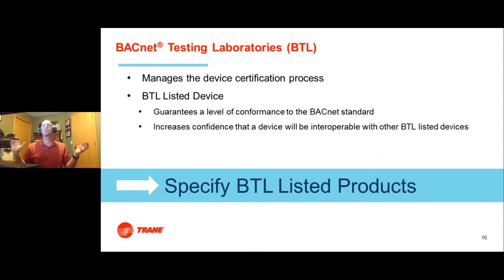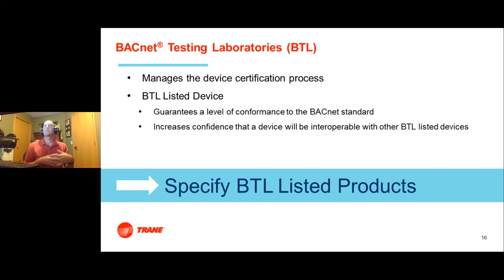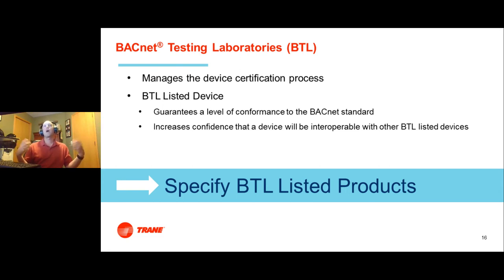As we talked about open standards, there's a testing arm for BACnet called BACnet Testing Laboratories, or BTL. You submit a product, it goes through standardized testing, and if it passes it becomes a BTL-listed device. This really helps increase our confidence that we'll have good interoperability between BTL-listed devices. We highly recommend that if you're involved in specifications or looking for products, look for ones that have actually gone through the testing and are BTL-listed.